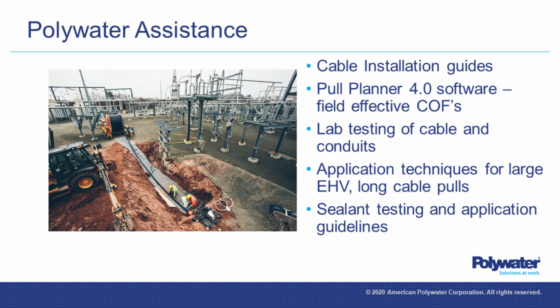So if you go to cable manufacturers' installation guides, or into the syllabus or addendum on the pull planner, you'll see the Rifenburg equations mentioned. These are the only mathematical equations used to calculate how much ending tension and sidewall pressure you'll have on a cable pull. Now the big difference is that back in the day, if we talk about using old, outdated data...